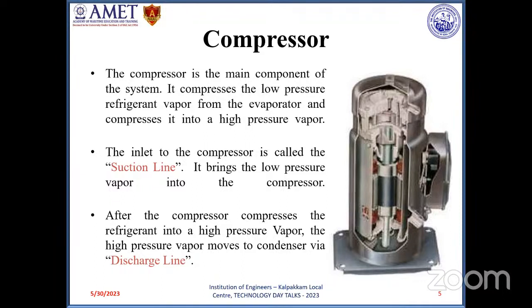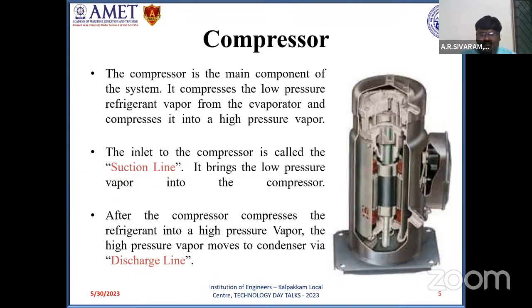Coming to the functioning of the compressor, the refrigerant enters the compressor as a low pressure vapor. It gets compressed and leaves as a high pressure, high temperature superheated vapor. The refrigerant entering the compressor should be in vapor state, because a compressor cannot compress a liquid. If the refrigerant enters the compressor in liquid state, it is likely to cause liquid slugging and failure of the compressor. So the refrigerant should enter as a low pressure vapor, and after compression, it leaves as a high pressure, high temperature superheated vapor.